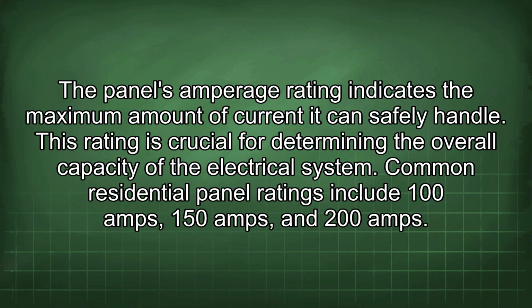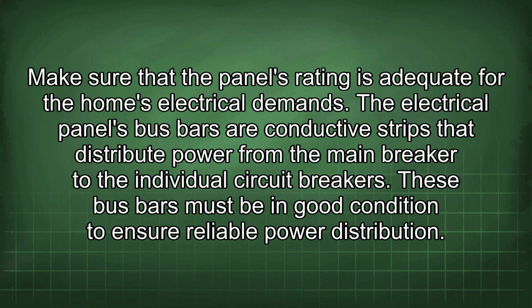The panel's amperage rating indicates the maximum amount of current it can safely handle. This rating is crucial for determining the overall capacity of the electrical system. Common residential panel ratings include 100 amps, 150 amps, and 200 amps. Make sure that the panel's rating is adequate for the home's electrical demands.